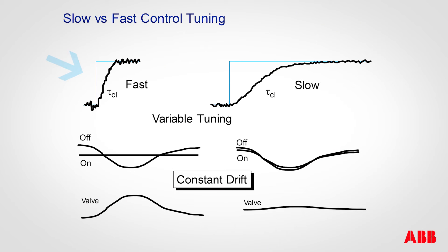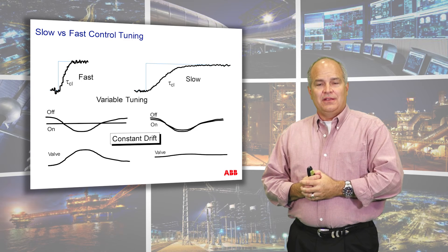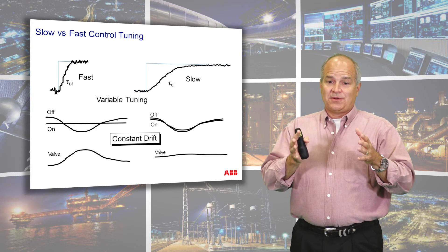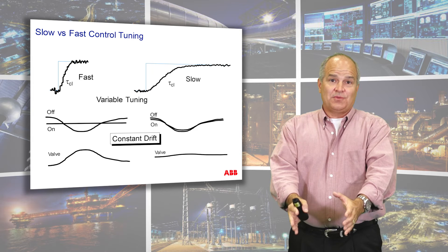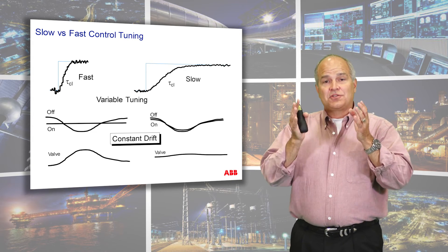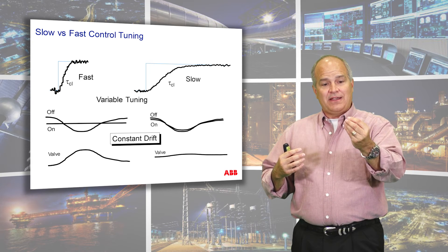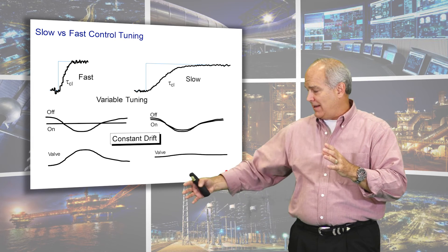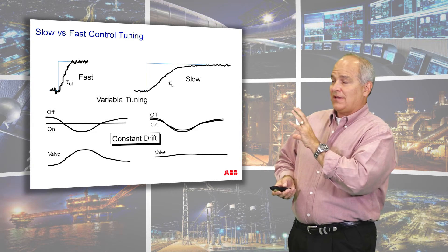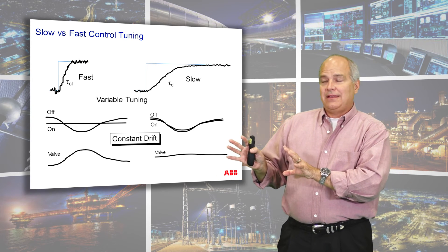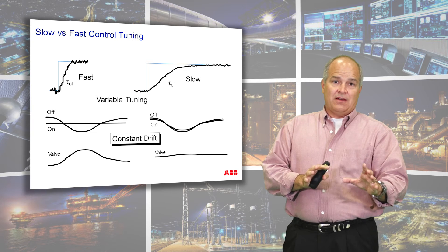If I've tuned the loop fast as compared to the low frequency disturbance, I'm able to redirect that energy into the actuation device. A disturbance never really goes away — it just shows up someplace else. So the disturbance will either show up in the process or show up in the actuation device. If you don't want it to show up in either place, you need to track down the source and remove it at the source. Whenever you can fix a disturbance by finding its root cause, it can have a huge cascading impact all the way through your process. If I've tuned my loop fast, I'm able to redirect the energy of the lower frequencies into my valve or final control element.